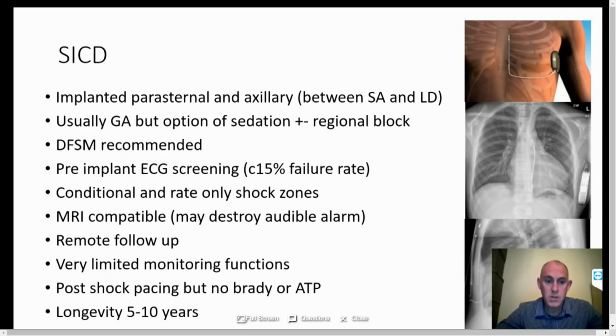This is because the device senses from the surface ECG. It has conditional and rate-only zones, but they're both shock-only. It is MRI compatible, although an MRI may destroy the audible alarm, and it does have a remote follow-up option, although not with quite the same user friendliness as a transvenous device.